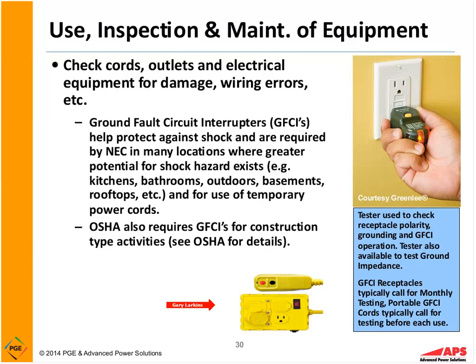So are we testing these things? In your home, when is the last time you tested the GFCI by pushing the test button? If you look at the receptacle or the instructions, which I really ask you to do, in many cases it may say test monthly, or please follow the manufacturer's recommendations if they give a different test schedule. Now, up here in this picture, we can see here's a little receptacle and GFCI tester. Not only used to test the GFCI, it has a little test button there, the yellow test button, but it also has lights on there to tell me whether my receptacle's wired properly. I bet a lot of folks have GFCIs in, especially the older ones, which were miswired.